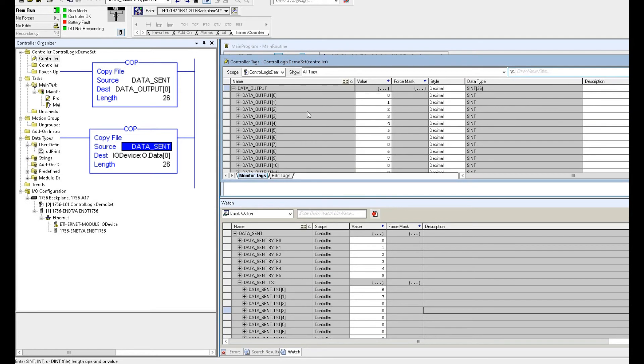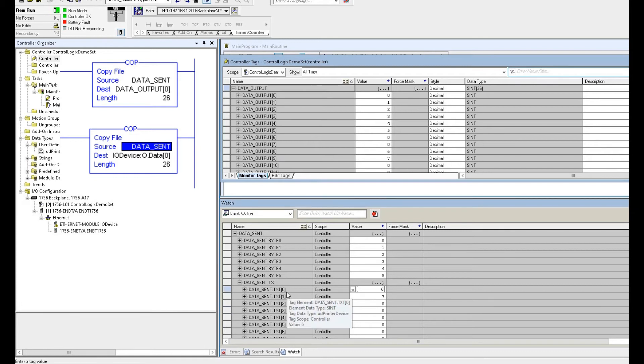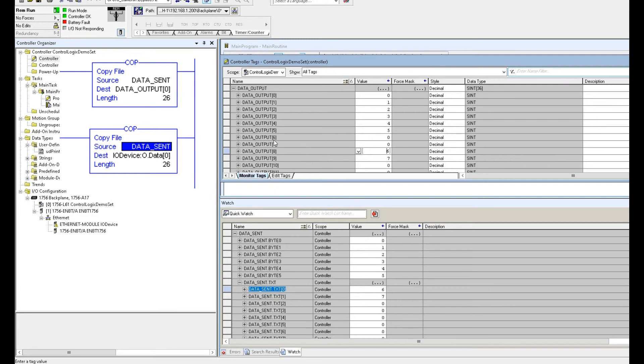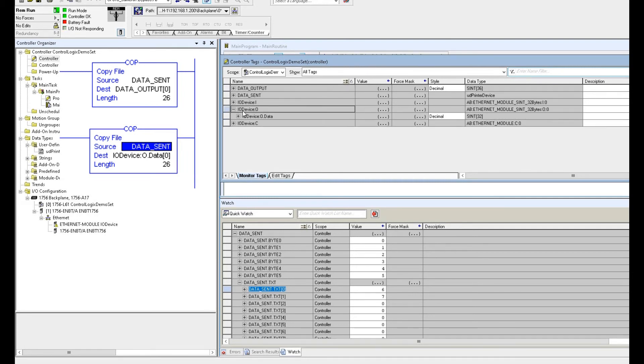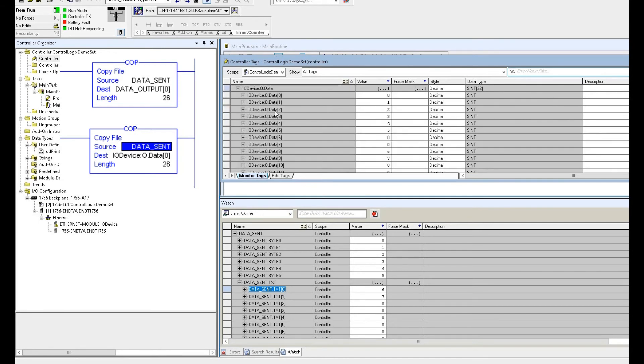So that is the data output. It starts from zero, one, two, three, four, five. But from here, number six and number seven are zero. The text value that was written is actually going into position eight rather than position six. We can see the same problem when we go to the output — IODevice output data — the same problem: number six and number seven are zero.